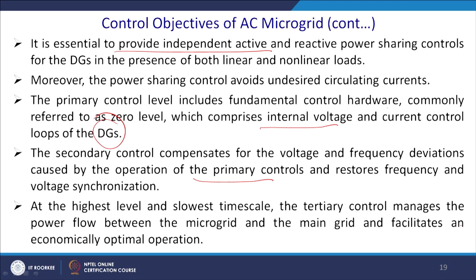The primary control level includes the fundamental control of hardware, commonly referred to as level zero, which comprises the internal voltage and current control loops of the distributed generators. Secondary control mainly compensates the voltage and frequency deviation caused by the operation of the primary control and restores the frequency and voltage synchronization. And the highest level, which has the slowest time scale, the tertiary control, manages the power flow between the microgrid and the main grid and facilitates economical operation in this case.